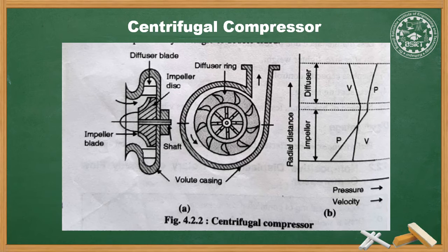A single stage compressor can develop a pressure ratio of 4 to 1, and up to 10 to 1 with the help of a multi-stage centrifugal compressor. Rotary compressors are used in oil refineries, petrochemical plants, natural gas transmission, refrigeration plants, and supercharging of SI and CI engines. In gas plants where the compressed air or air to be compressed is filtered, rotary compressors are used widely.